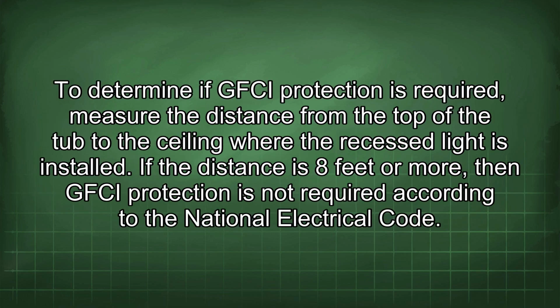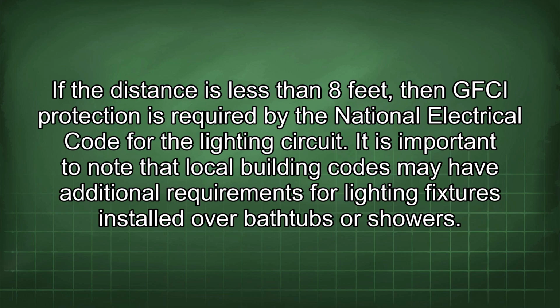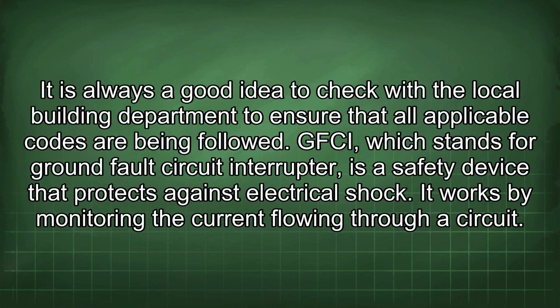To determine if GFCI protection is required, measure the distance from the top of the tub to the ceiling where the recessed light is installed. If the distance is 8 feet or more, then GFCI protection is not required according to the National Electrical Code. If the distance is less than 8 feet, then GFCI protection is required by the National Electrical Code for the lighting circuit. It is important to note that local building codes may have additional requirements for lighting fixtures installed over bathtubs or showers. It is always a good idea to check with the local building department to ensure that all applicable codes are being followed.